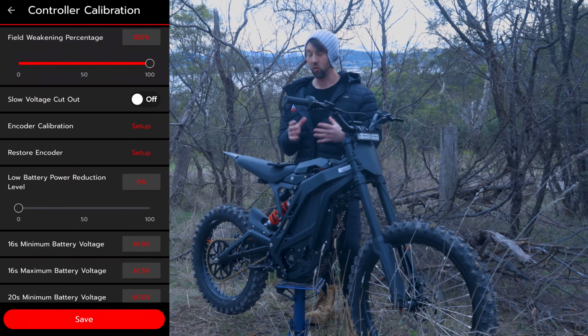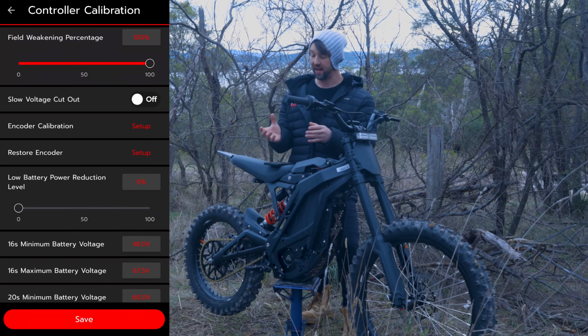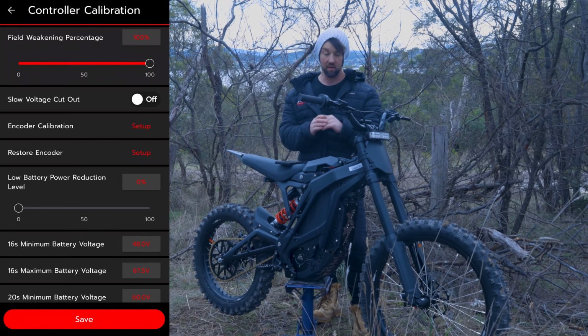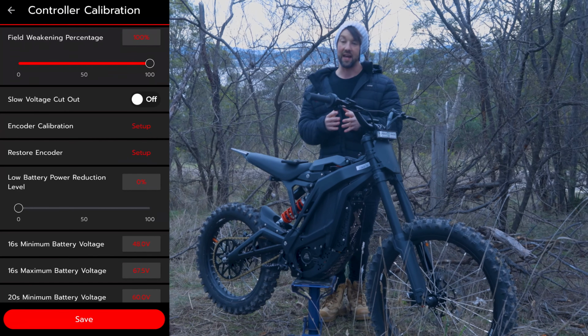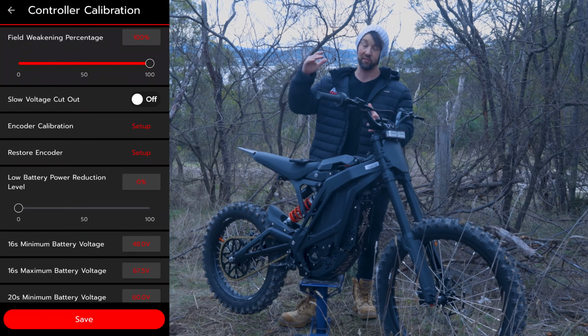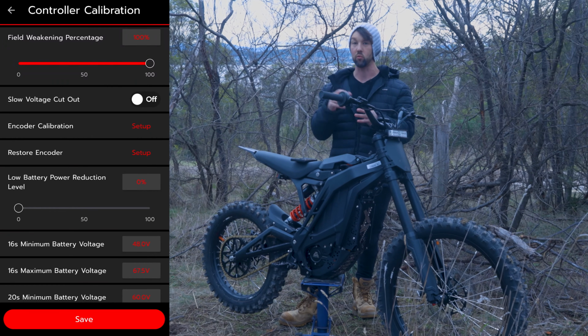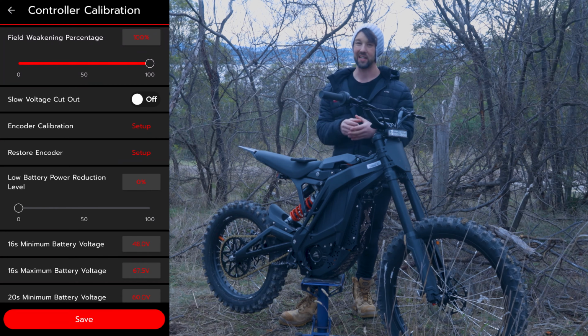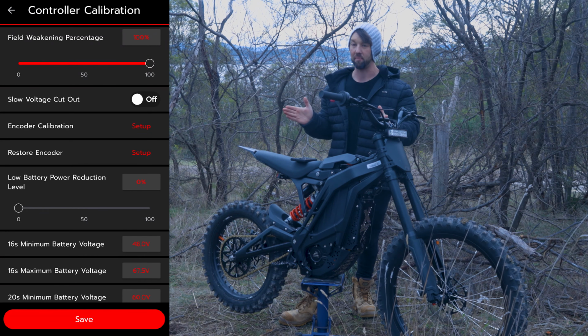The other one is low power reduction. How that operates, leave it at 0% or up it if you want to. What it does is as the controller sees the voltage coming down, it'll start to reduce the maximum power, and this essentially means that you'll get 100% use out of the battery.